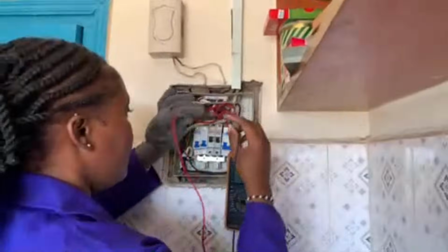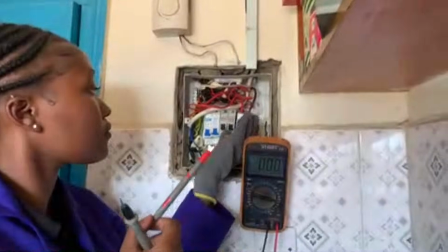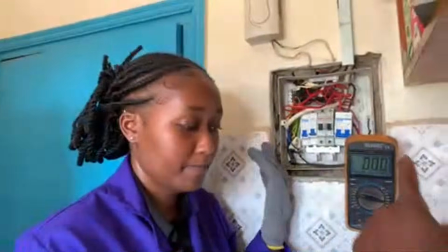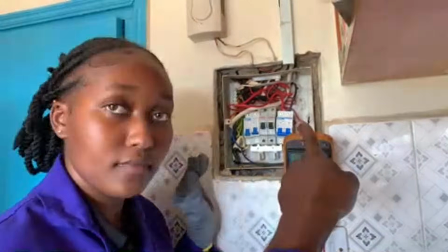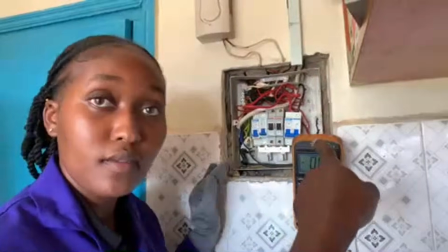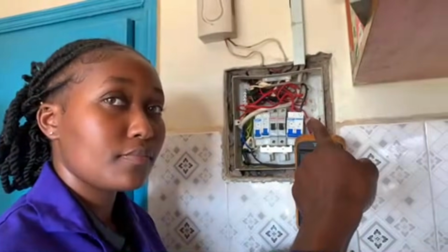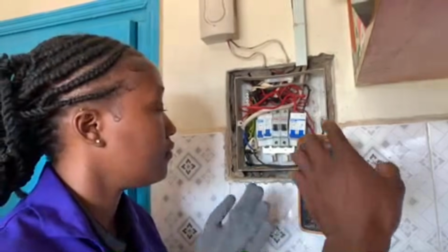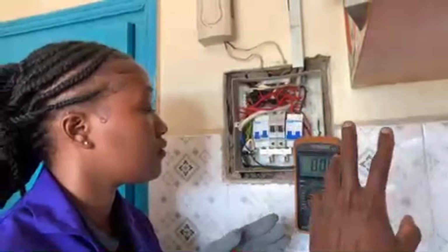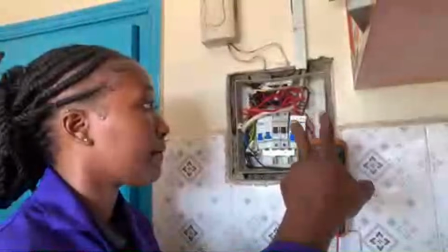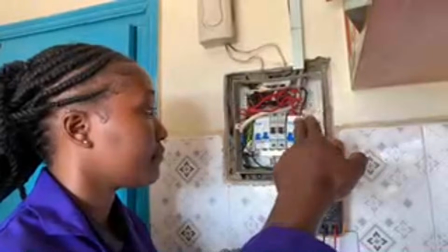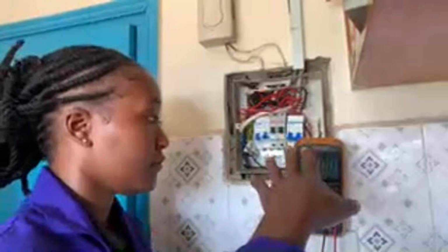Amazing, now let me explain something. The reason we tested on the screws is if we get an output there, it means the screws are in contact with the wire itself. If it were in contact with the insulation instead, assuming you had done a bad job, it would have given us a very low voltage or even zero. So that is a good job.